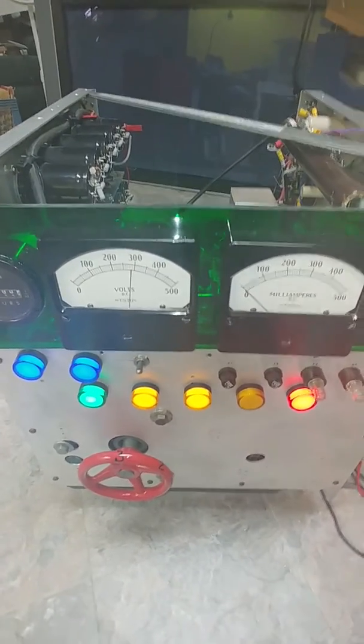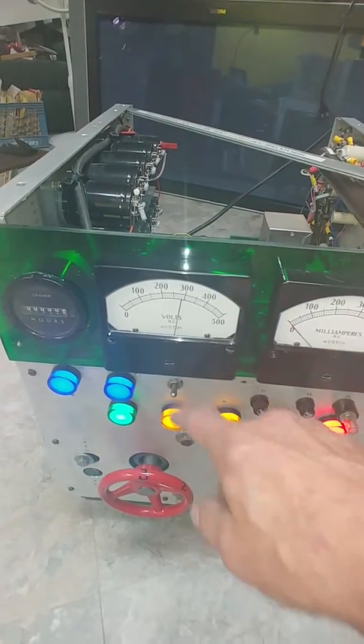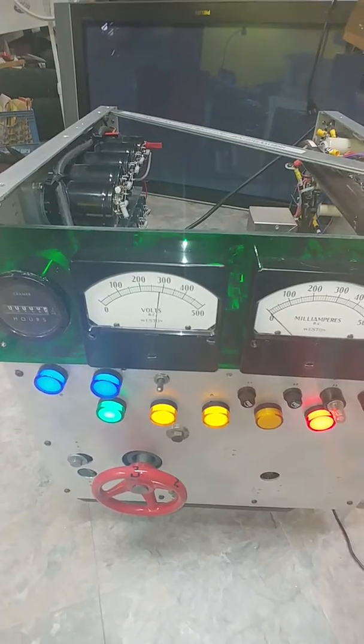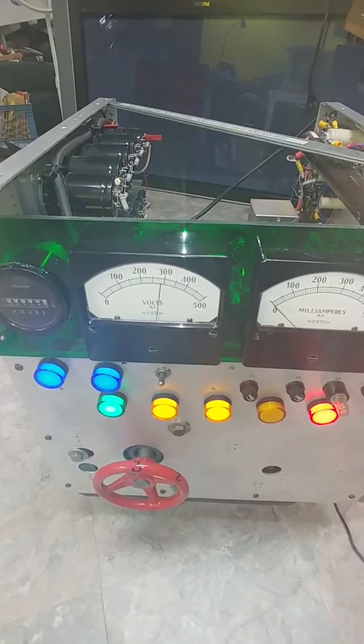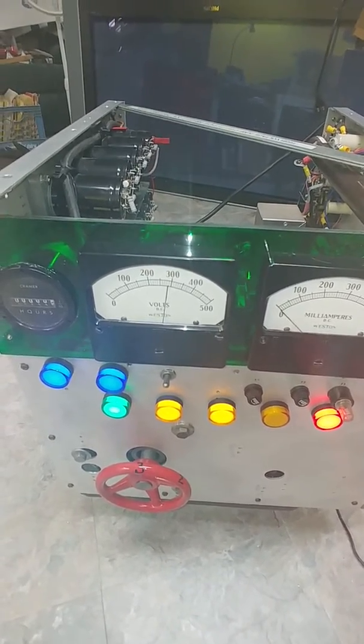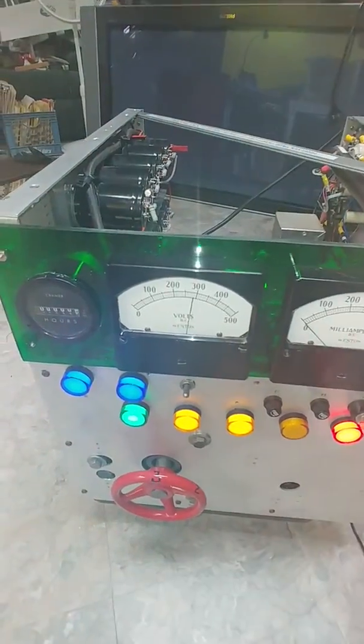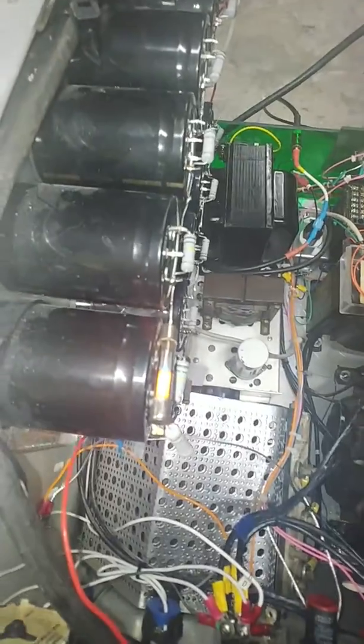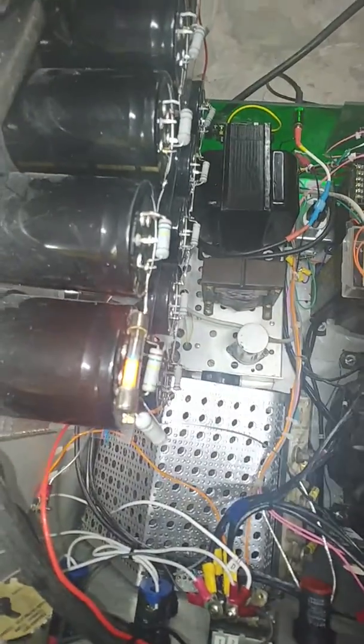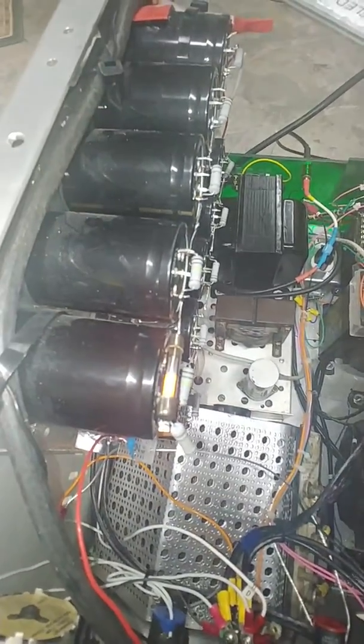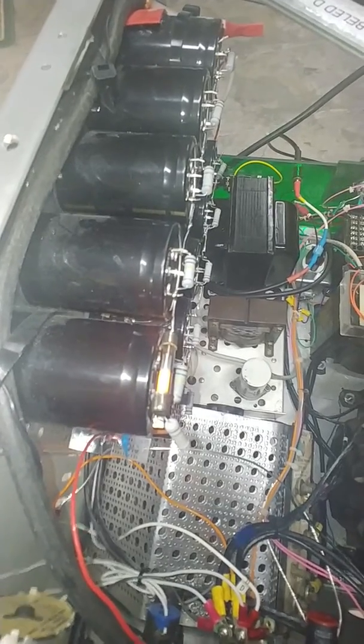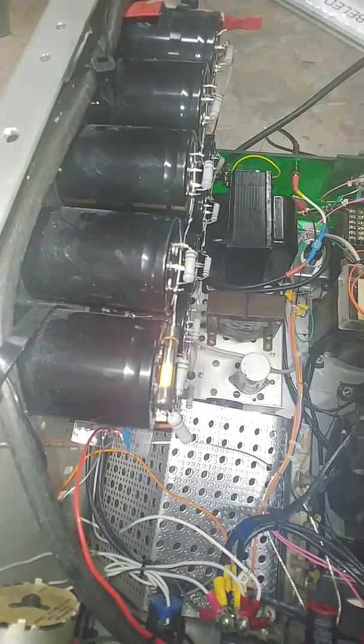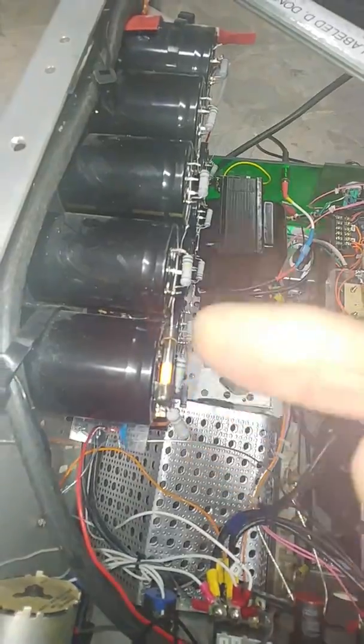So that's what happens. But I'm particularly happy with the fact that the dump relay, which is tied to this switch, when I turn off the relay, its normally closed position drops 8,000 ohms across this capacitor bank and discharges it. For safety, one of the things I do all the time is put a neon in the system here so I can control the operation of the supply and be reminded that this thing is hot, hot.